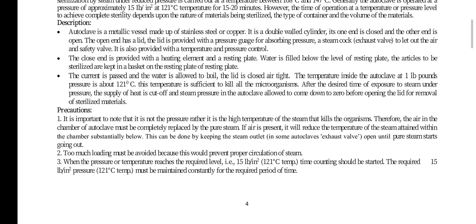Too much loading must be avoided because this would prevent proper circulation of steam. When the pressure or temperature reaches the required level, that is 15 lb per inch square, time counting should be started. The required 15 lb per inch square pressure must be maintained constantly for the required period of time.